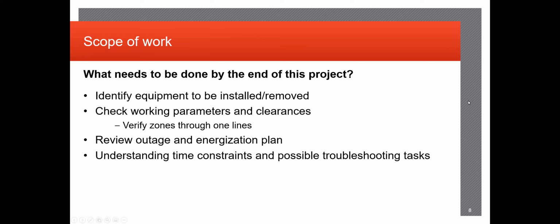So identifying the scope of work, pretty much it's fairly straightforward. Identifying the equipment that needs to be installed or removed, checking the working parameters and clearances. So this is a big one because a lot of times, especially on a brownfield site, in which case a brownfield is pretty much a substation that had been previously placed into service and had been running for some time, and it is going to be taken out of service, or even just a portion of it, to upgrade, modify, whatnot. Identifying the parameters and the clearances is important so that you're not touching any in-service equipment while you're doing your work, because that can lead to injuries, loss of power to customers, stuff like that, stuff that nobody wants to see.